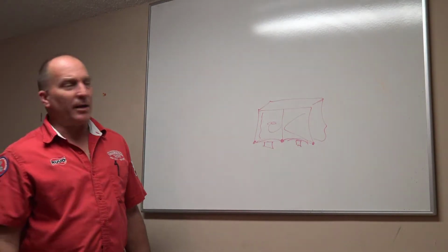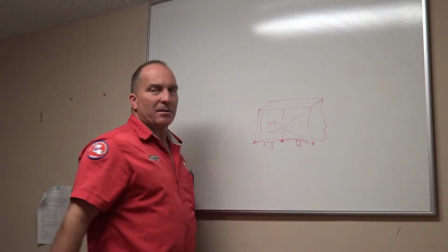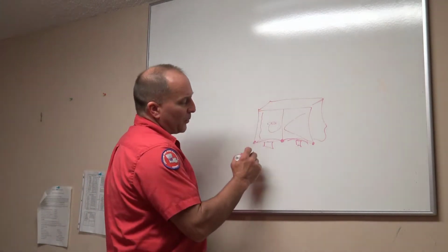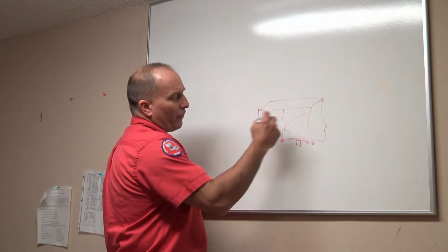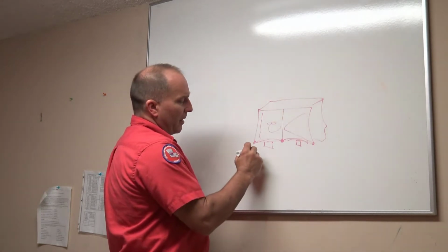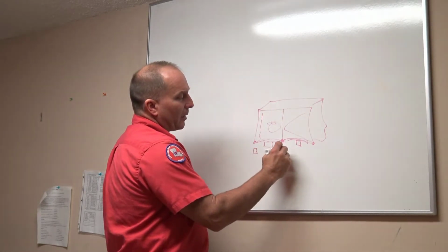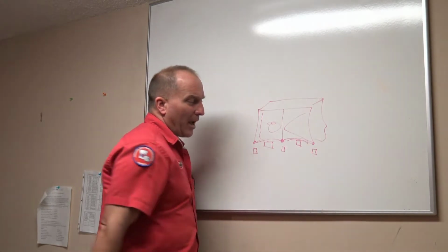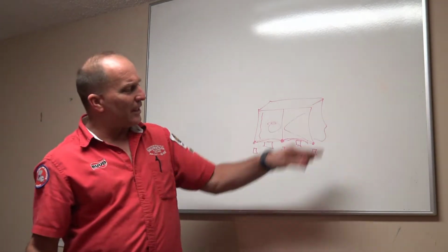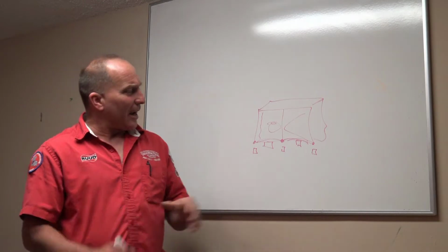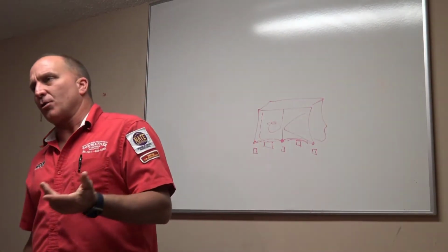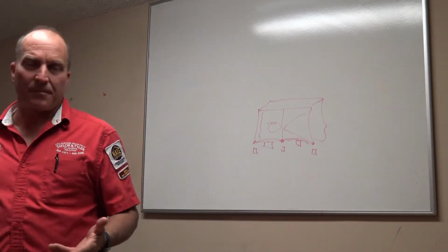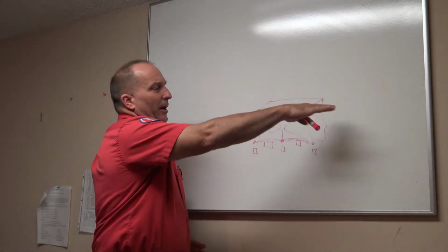But instead of putting a total of 6 blocks underneath here, whoever it was put 2 blocks, and well, 4, one on each side of them. So I would put a block here, and a block here. We have foam blocks, and that would be on each side, so a total of 6 blocks. And I would put those blocks under the corners, so that is where your support is. That's going to keep your air handler straight.